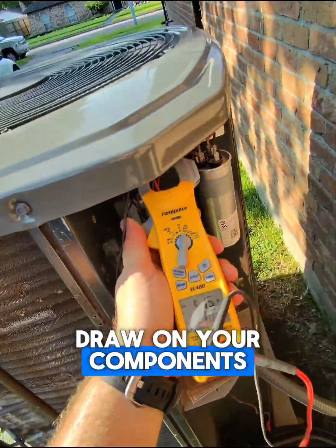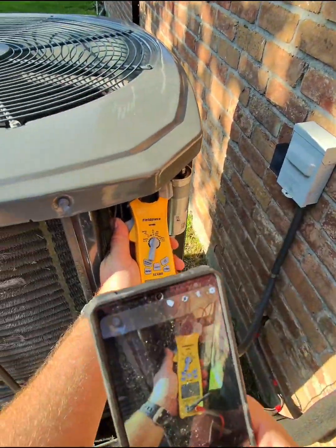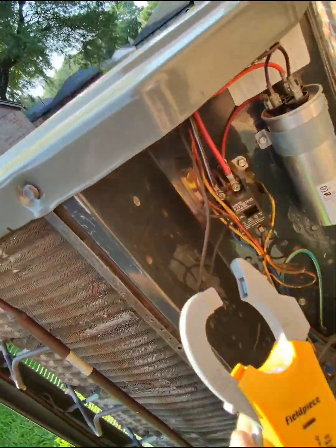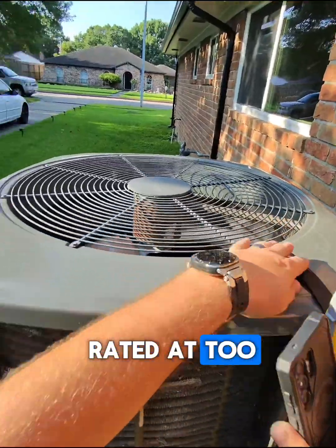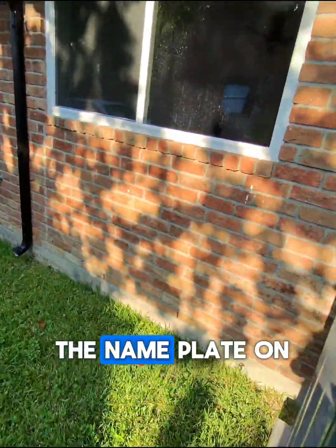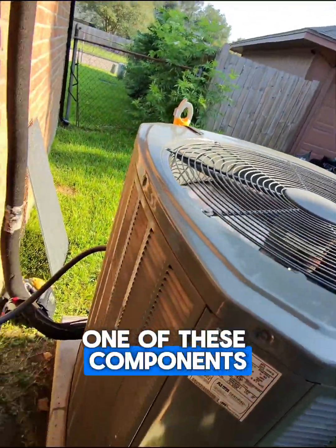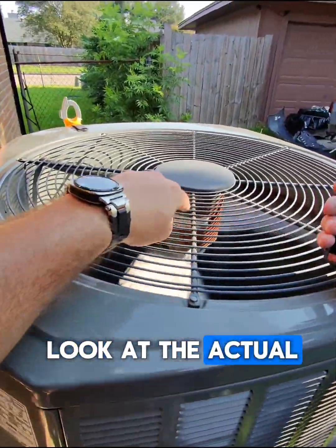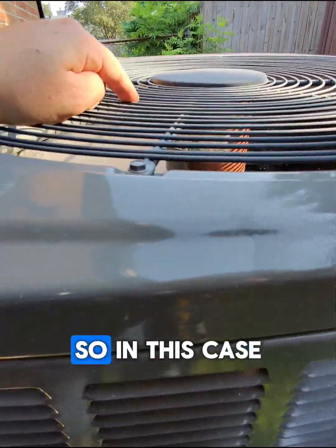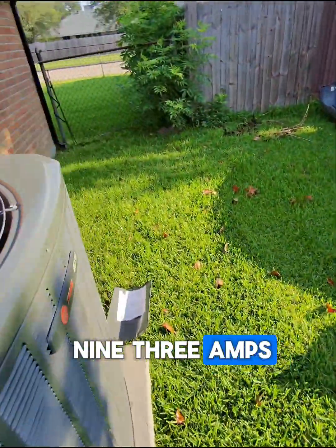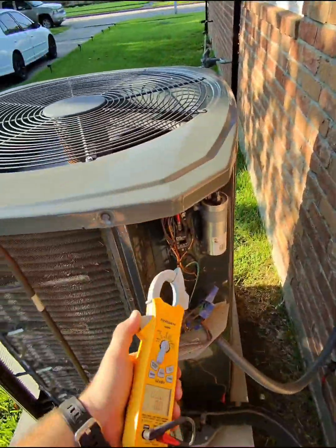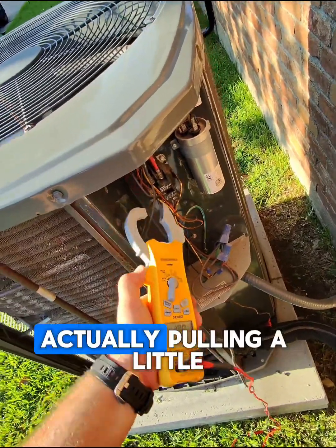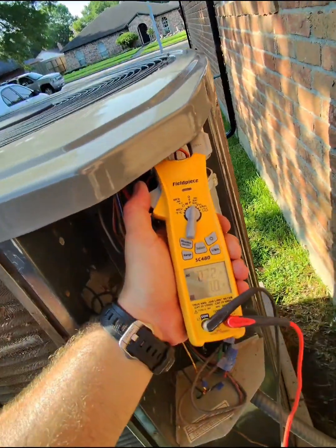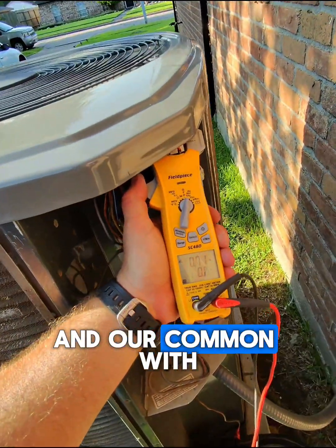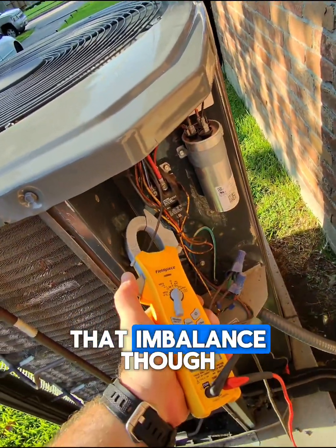You get an amp draw on your components. Compressor, fan, and you want to know what your components are rated at too, so you want to check your nameplates. Don't always rely on the nameplate on your unit, because you could have had one of these components replaced with an aftermarket one that has different ratings, so you always want to look at the actual component itself. So in this case it's rated at 0.93 amps. Actually pulling a little bit higher, but also our capacitor is weak. And our common is within spec. They don't like that imbalance though.